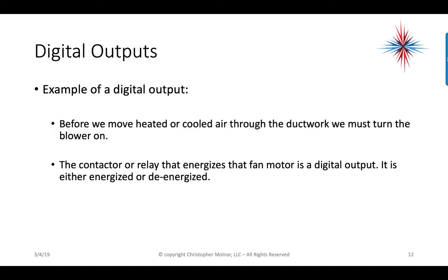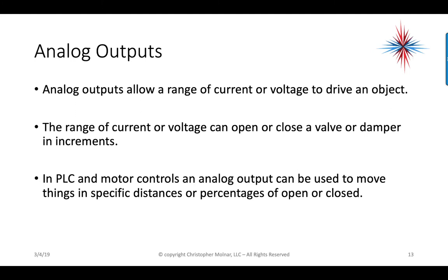An example of a digital output: before we move heated or cooled air through the ductwork, we have to turn the blower on. The contactor or relay that energizes the fan motor is a digital output — it's either energized or de-energized. Analog outputs allow a range of current or voltage to drive an object. The range of current or voltage can open or close a valve or damper in increments. In PLC and motor controls, an analog output can be used to move things a specific distance or percentage of open and closed — we're dealing with percentages.